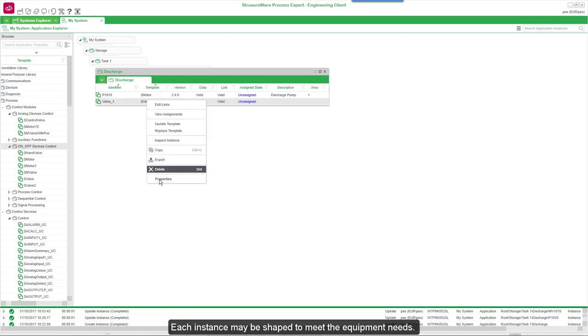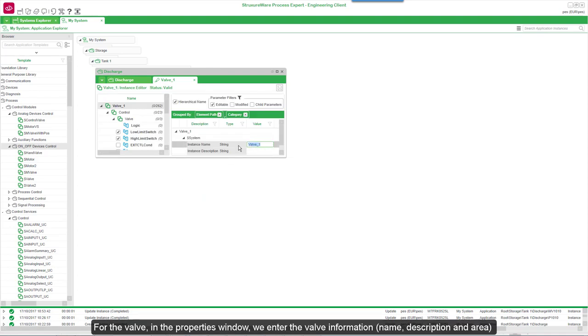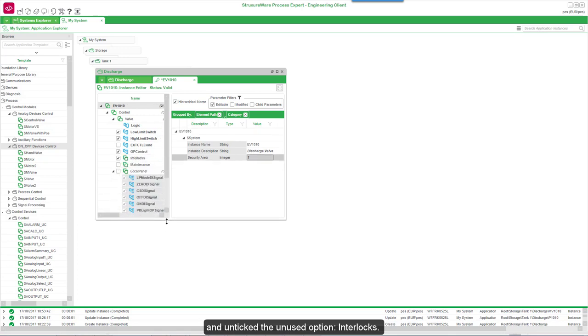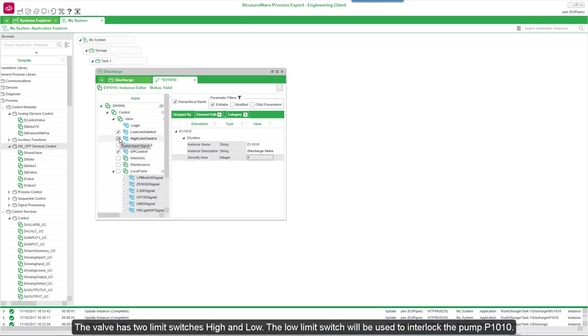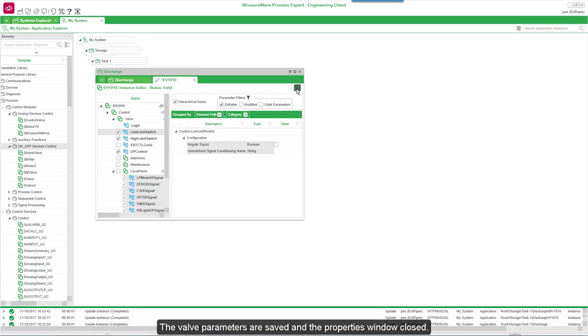Each instance may be shaped to meet the equipment needs. For the valve, in the Properties window, we enter the valve information: name, description, and area. We untick the unused option, Interlocks. The valve has two limit switches, high and low. The low limit switch will be used to interlock the pump P1010. The valve parameters are saved and the Properties window closed.